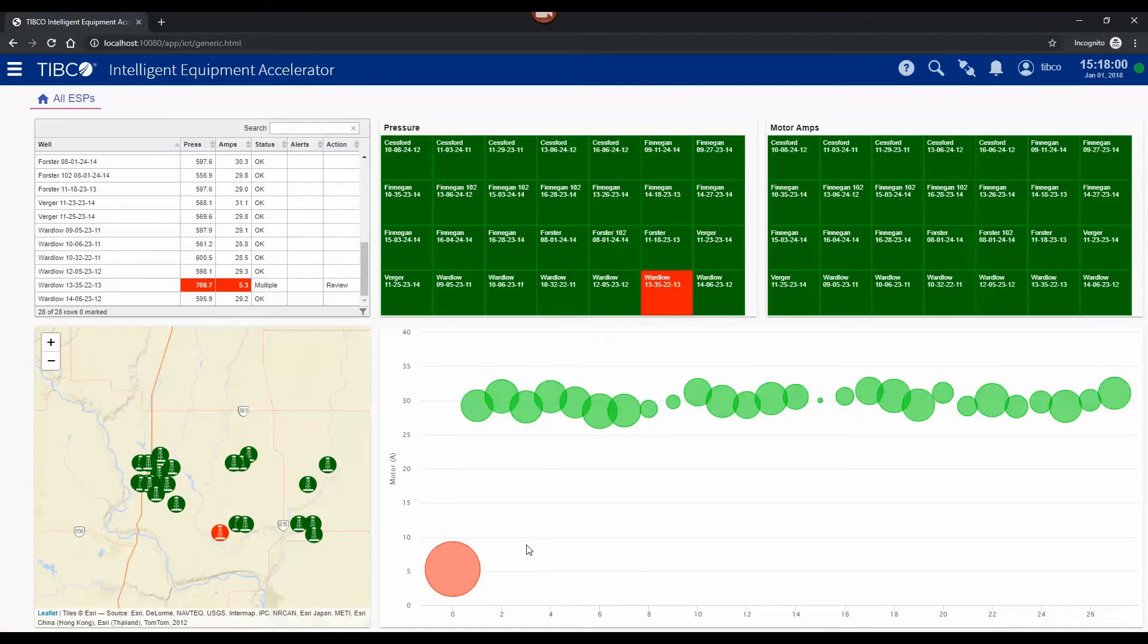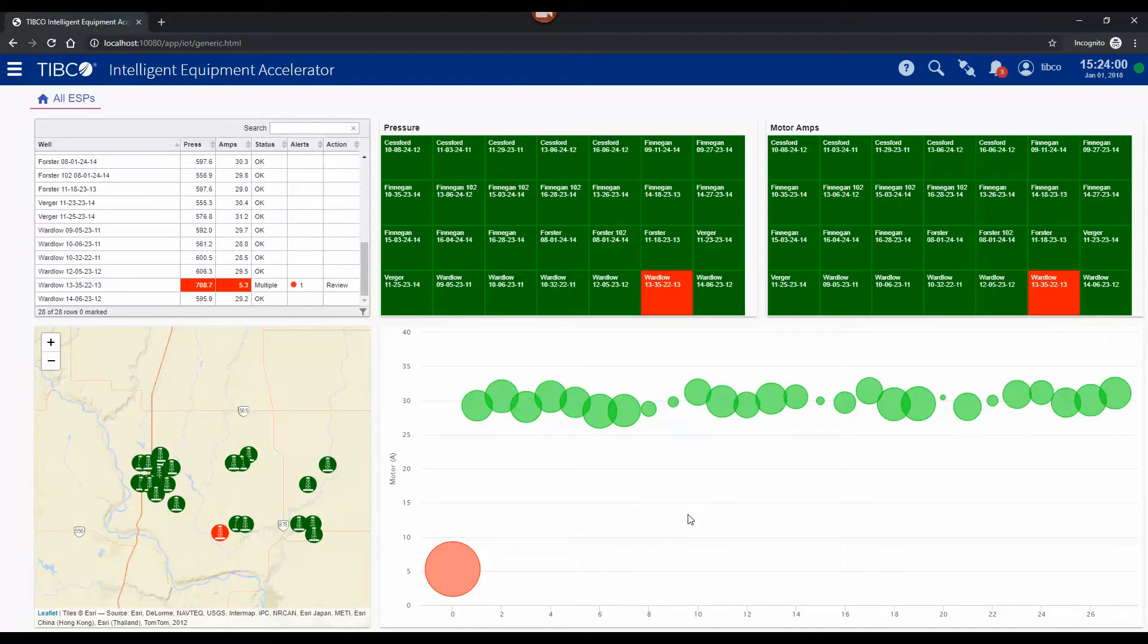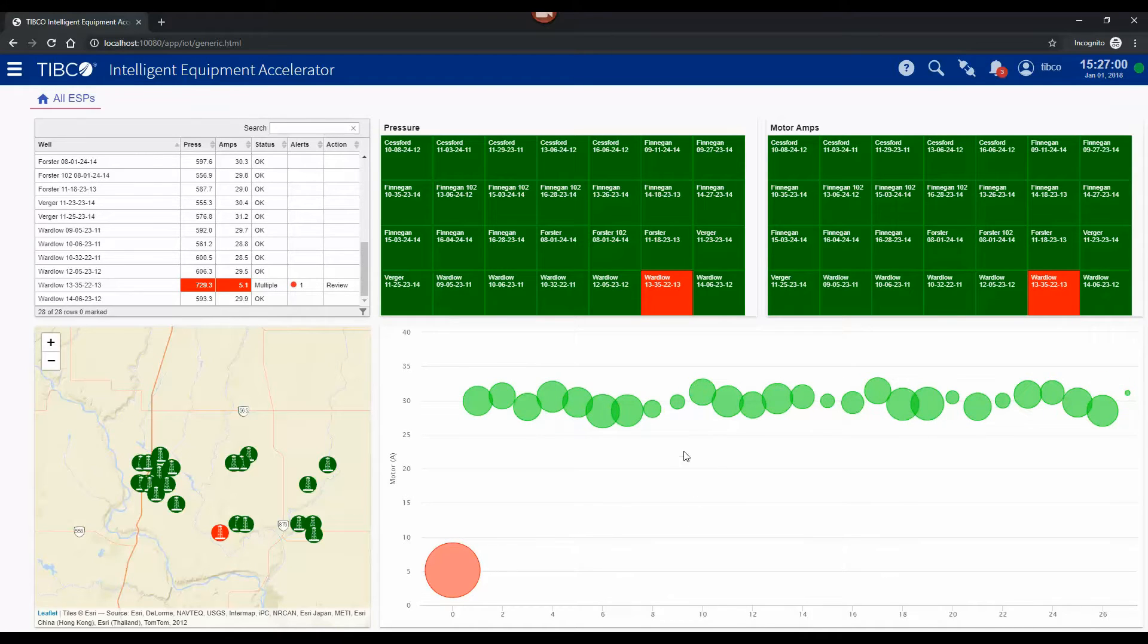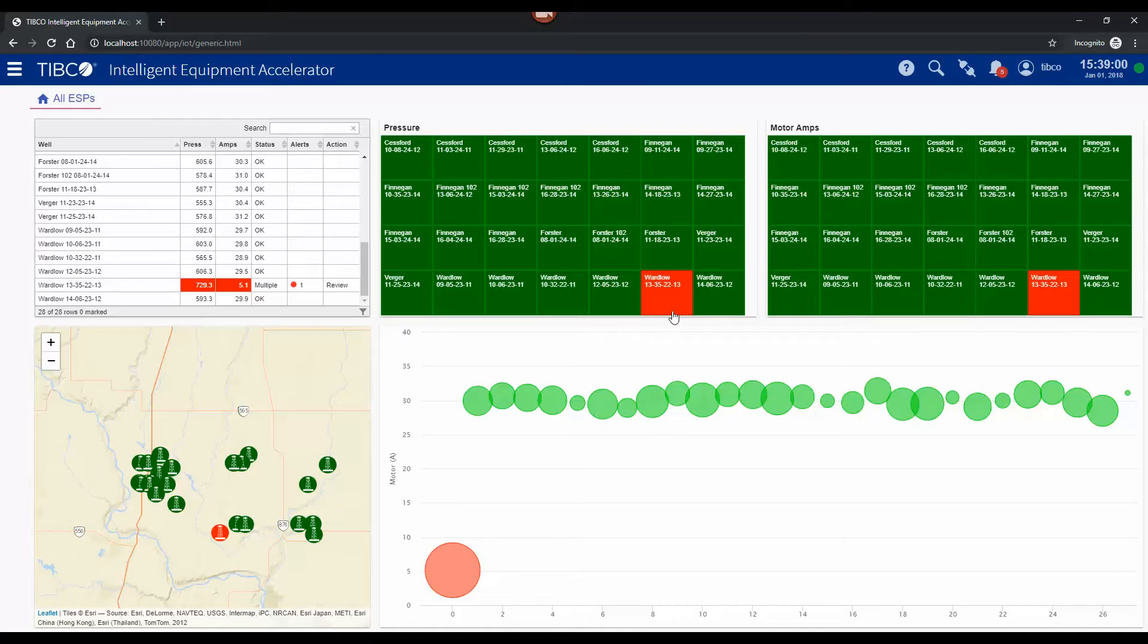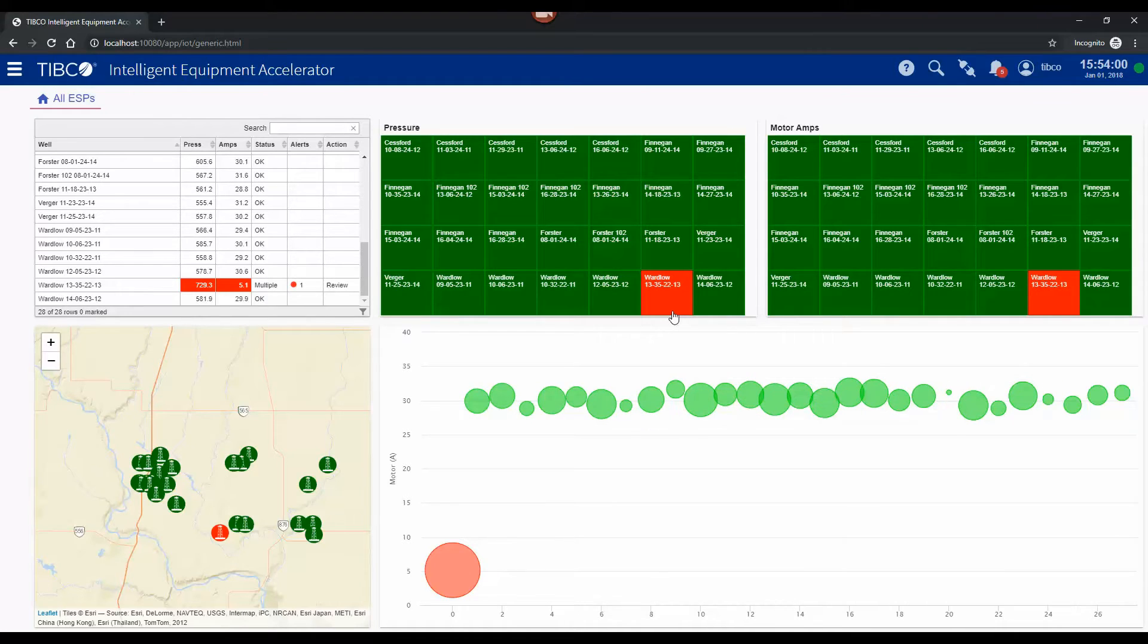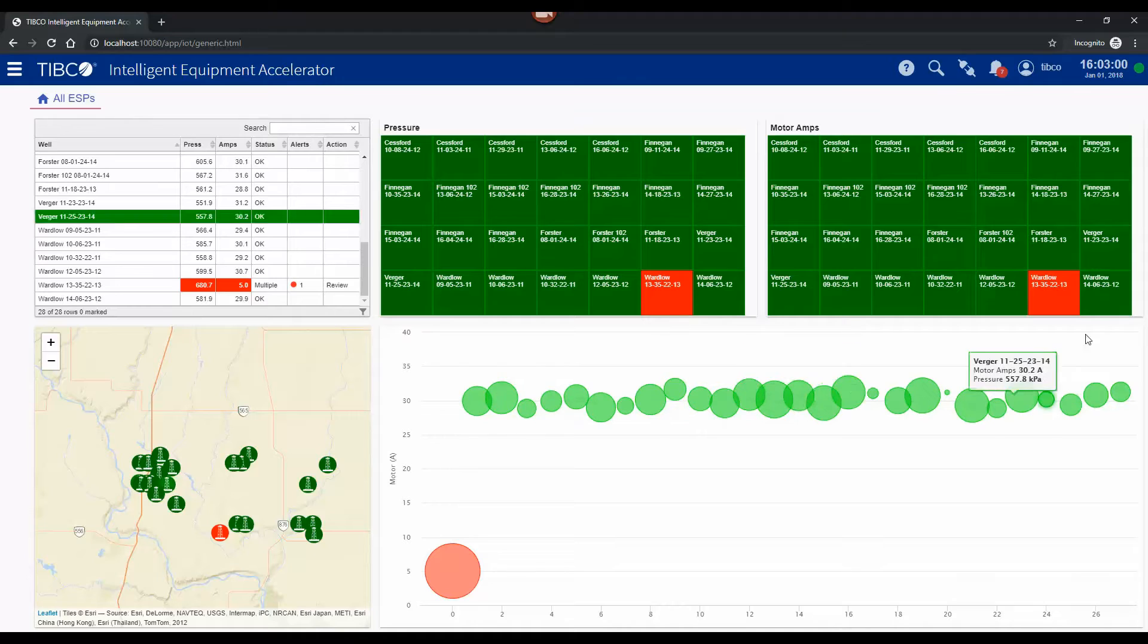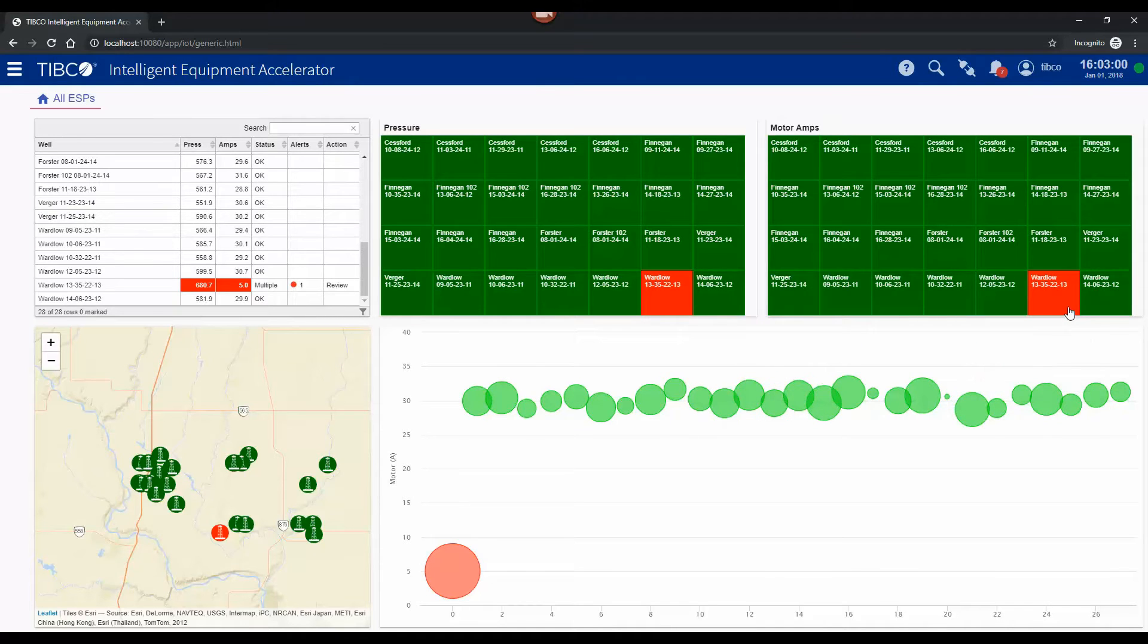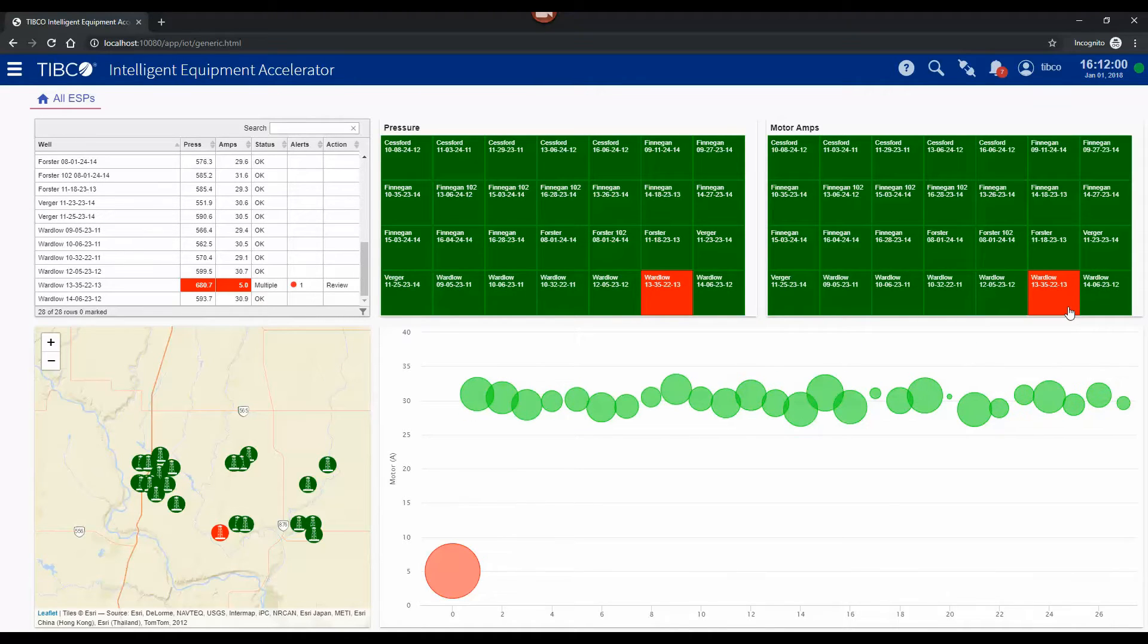So you can see we've got some red boxes now on the screen. Our pressure has now risen above 650 kilopascals and our motor amps has dropped below 15 amps.